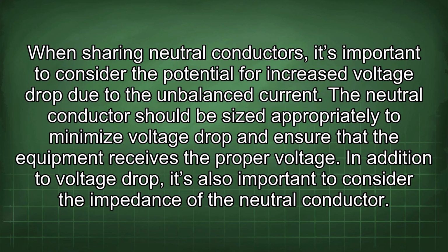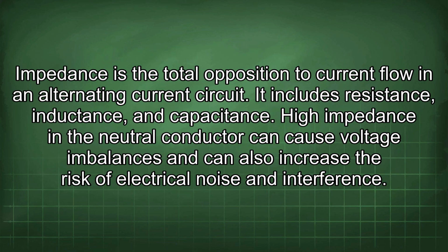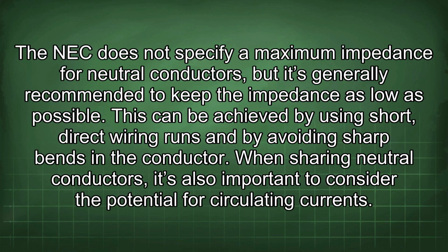In addition to voltage drop, it's also important to consider the impedance of the neutral conductor. Impedance is the total opposition to current flow in an alternating current circuit. It includes resistance, inductance, and capacitance. High impedance in the neutral conductor can cause voltage imbalances and can also increase the risk of electrical noise and interference. The NEC does not specify a maximum impedance for neutral conductors, but it's generally recommended to keep the impedance as low as possible.